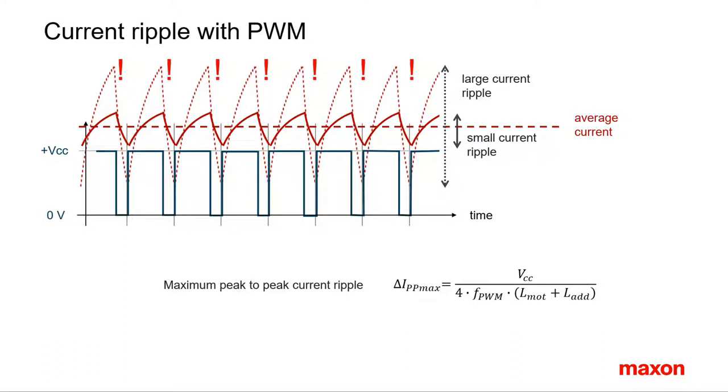The maximum current ripple can be approximated with this formula. The formula is easy to understand and hence the measures to be taken for reducing the amplitude of the ripple as well. For example, reduce the supply voltage. This reduces the maximum current increase within each PWM cycle. Allow less time for the current to react. This means increase the PWM frequency. Enhance the electrical time constant to dampen the current response. Place an additional inductance in the motor circuit.